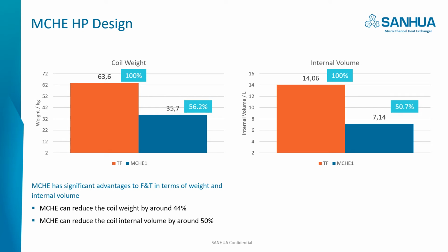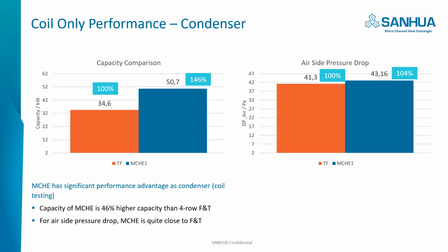We compare the coil weight and the internal volume of both heat exchangers. The advantage of microchannel is significant. Compared to the fin and tube heat exchanger, microchannel's weight can be reduced by around 44%. And for internal volume, the reduction is around 50%, almost half. Let's see the performance comparison between both heat exchangers.